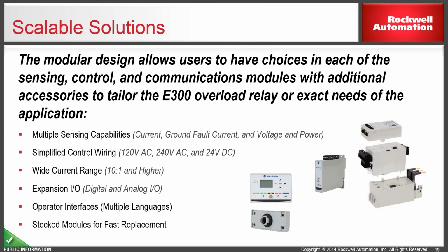We have various modules available: 120 volt AC, 240 volt AC and 24 volt DC. Depending on the choice, you can go for it, but most of the time in an MCC, we have 240 volt AC running, and you have to put in a separate power supply to give 24 volt DC. So most of the time we choose 240 volt AC. On the current transformer, there is a wide current range of 10 to 1. Expansion IOs we have in digital and analog. And then there is also an operator interface, which has a diagnostic station and an operating station, which you can see on the screen.